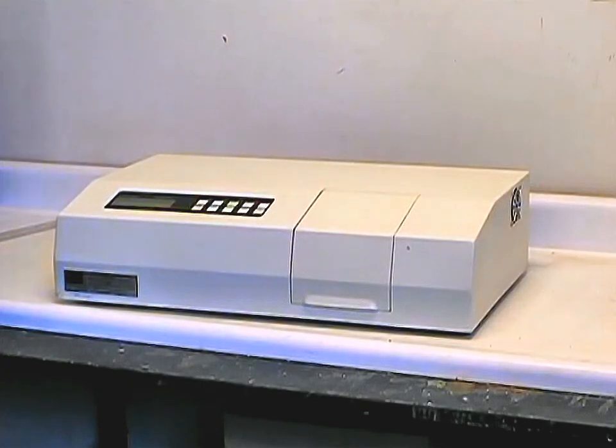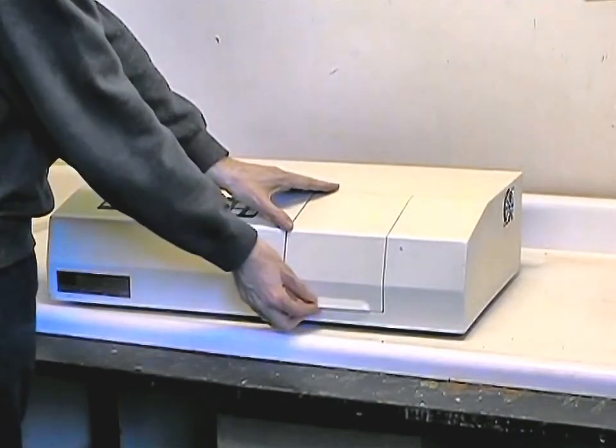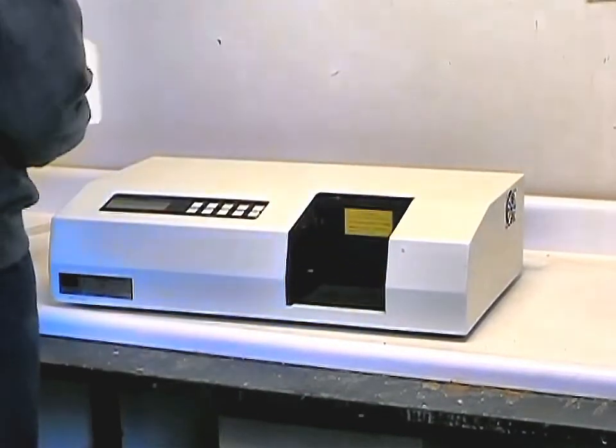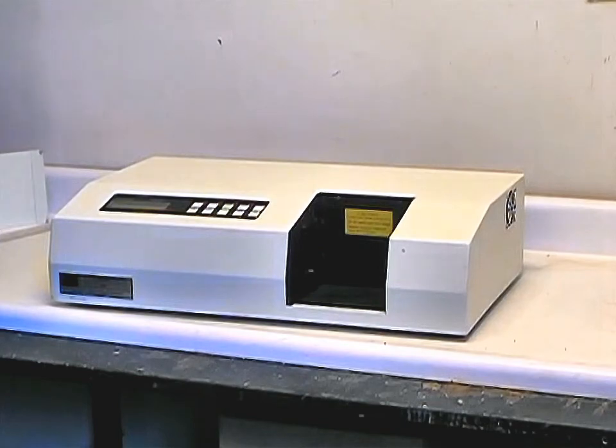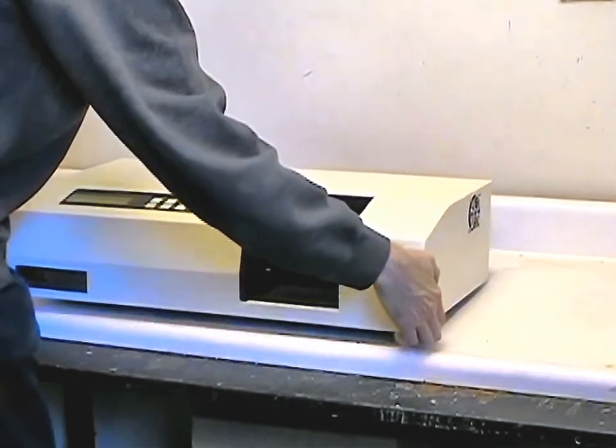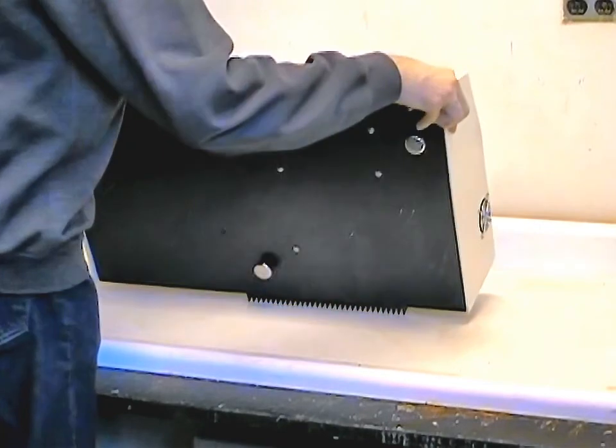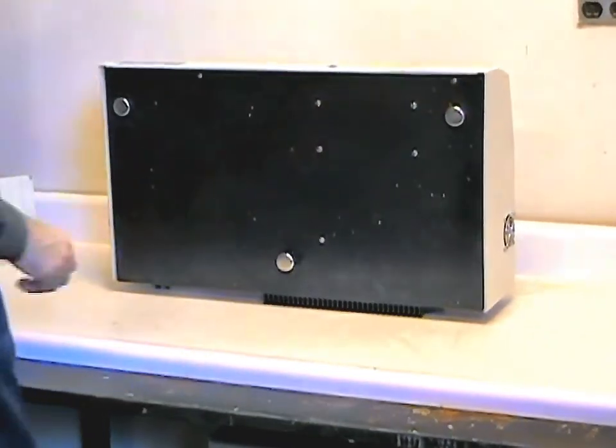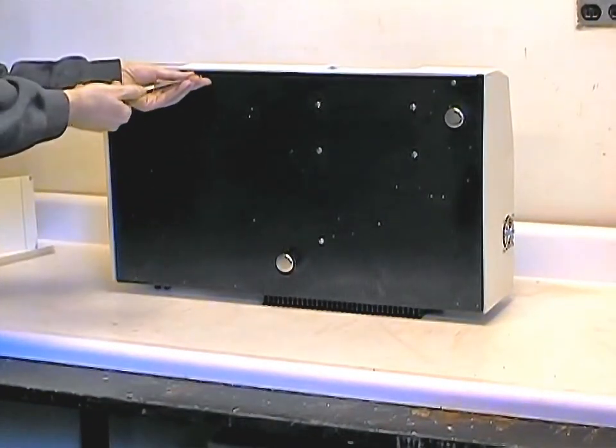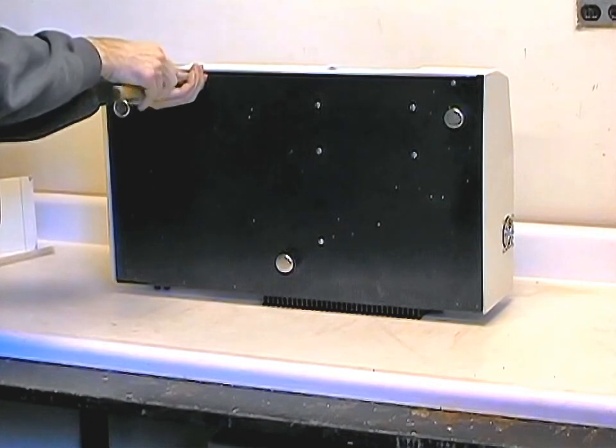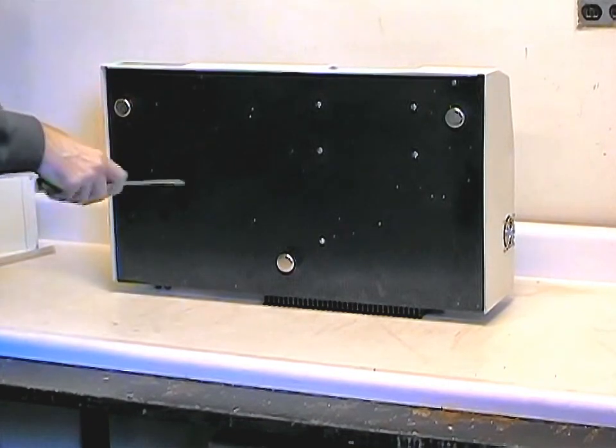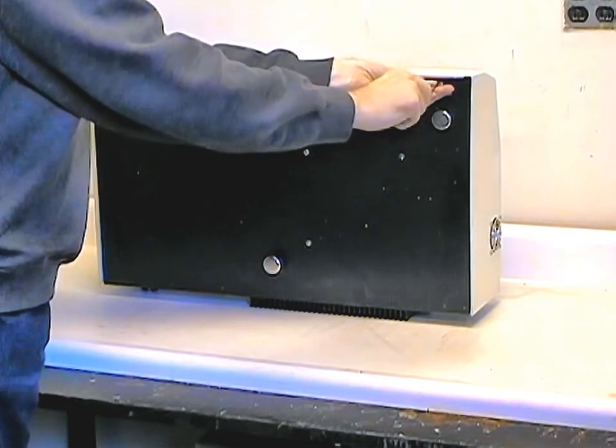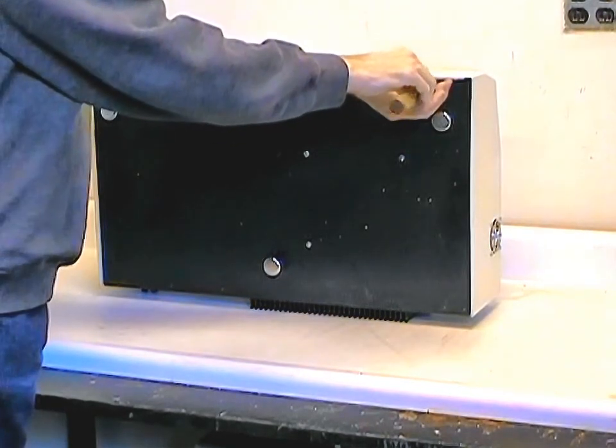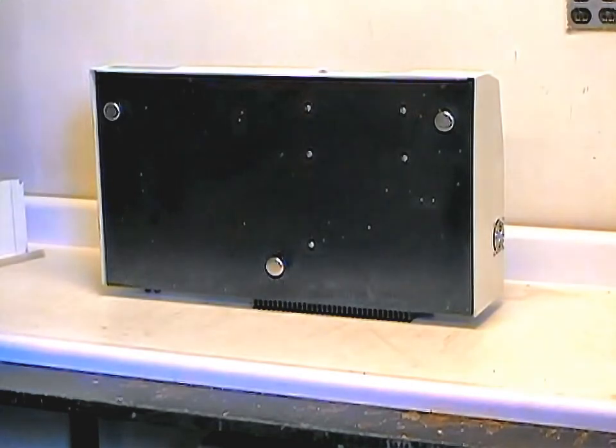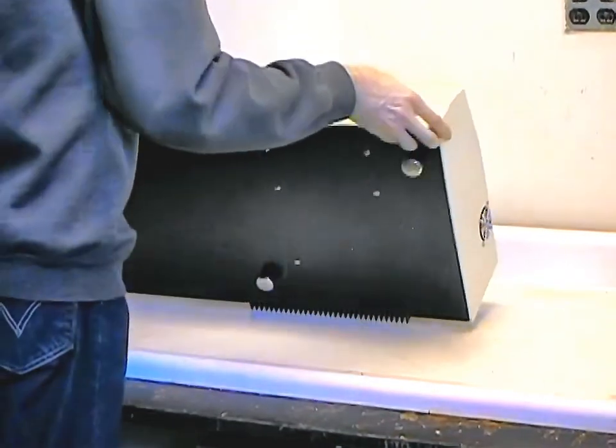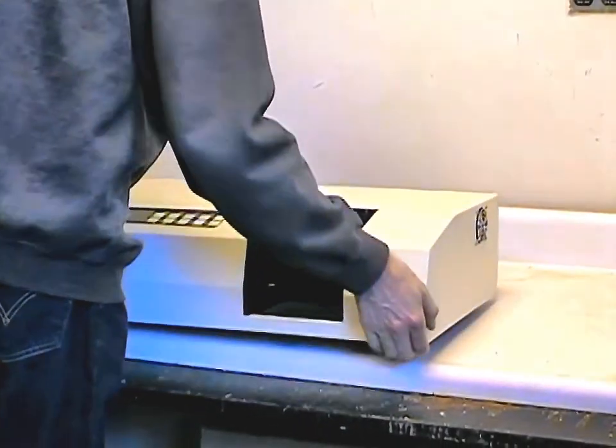When the instrument has been unwrapped from its protective plastic, remove the front panel, which is held in place with a little magnetic latch. Then it is necessary to tip the M500 backwards on its heat fins so that the lockdown screws for the cover can be removed with a flat screwdriver. Save these screws to secure the cover in place in case the M500 needs to be returned to Buck Scientific. Once the screws are removed, the instrument is gently lowered back into position.